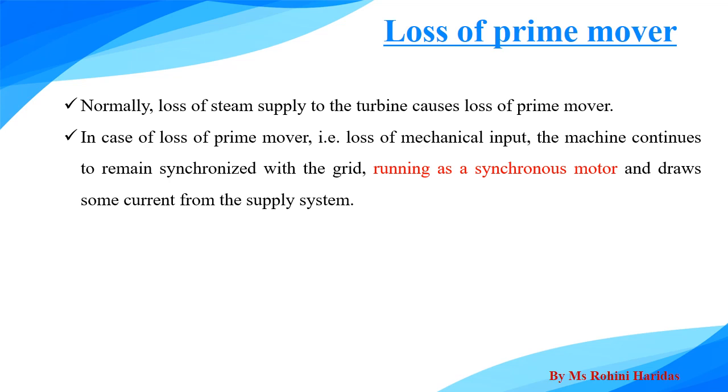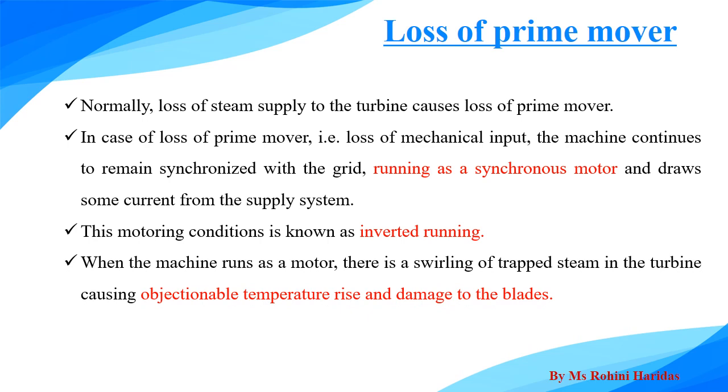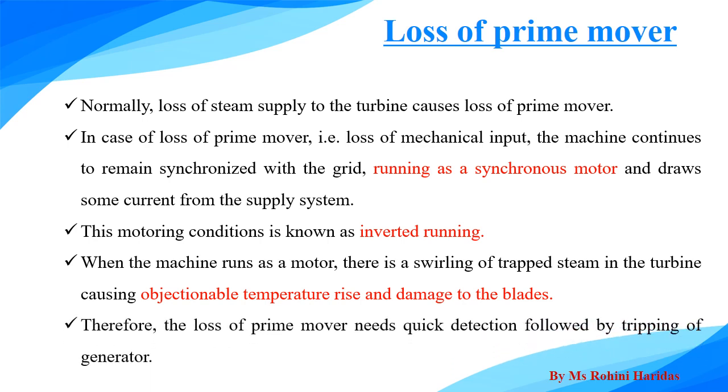The meaning is that instead of supplying energy to the power system, it will take the energy from the power system. When the machine runs as a motor, there is a swirling of a trapped steam in the turbine causing objectionable temperature rise and damage to the blades. Therefore, the loss of prime mover needs quick detection followed by tripping of the generator. The reverse power relays are used for the protection against the loss of prime mover.